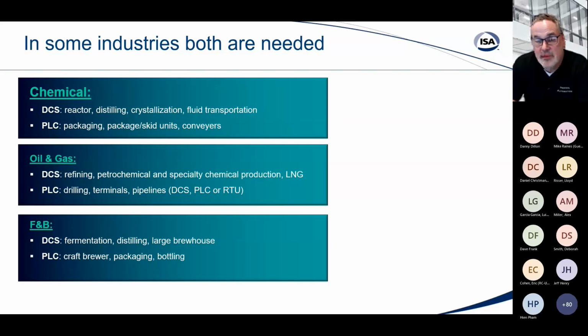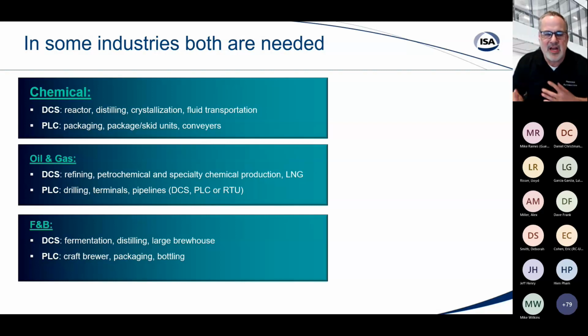In some industries, both are really needed. If you take the chemical industry, you can see there's a need for DCS and there's a need for PLC. Typically, the DCS is going to be running the reactors, the distillation, crystallization, fluid transportation, whereas the PLC will be managing possibly skid packages, packaging units, conveyors, those different types of controls. Same thing in oil and gas, food and beverage. You could go to pharmaceutical. You could talk about a lot of different industries where you'll see both DCS and PLCs in the facility. They just handle different parts of the facility.